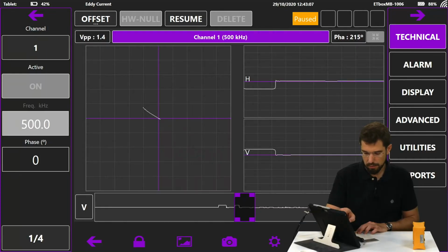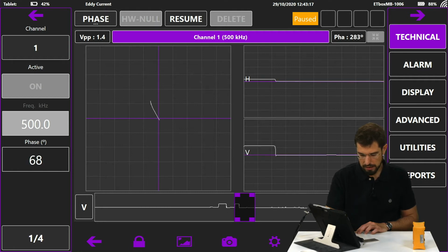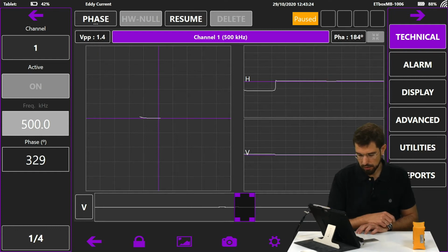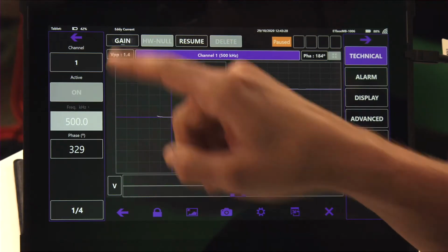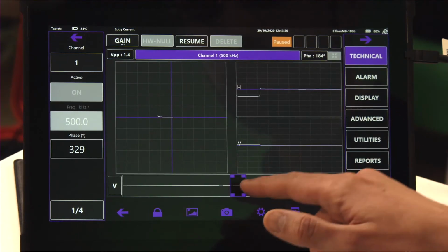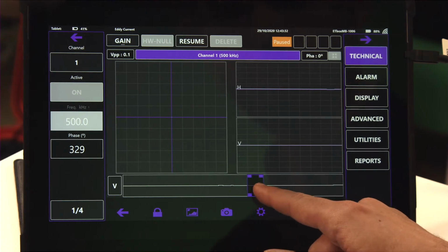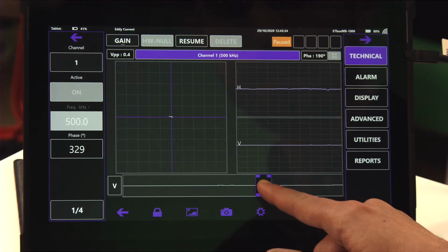The first thing we have to do is to change the phase. We can also see the phase in this menu, which is 0 degrees in this case. And we can rotate the signal via the touchscreen in order to assign the phase we need to it. As we're seeing, we put the liftoff signal horizontally, which is a common way to calibrate the phase. Now we calibrate gain. In order to do that, we have to search the area where we have acquired the notches.